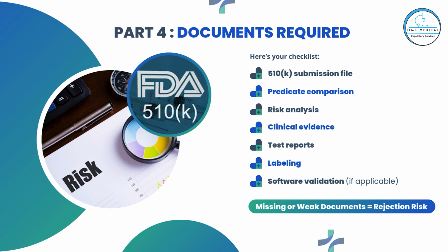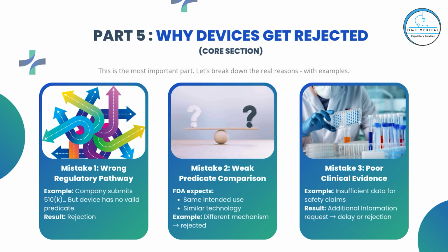Part 4. Documents required. Here's your checklist. 510K submission file: predicate comparison, risk analysis, clinical evidence, test reports, labeling, software validation, if applicable. Missing or weak documents equals rejection risk. Part 5. Why devices get rejected, core section. This is the most important part. Let's break down the real reasons with examples.